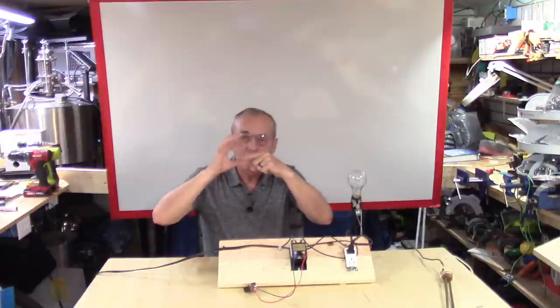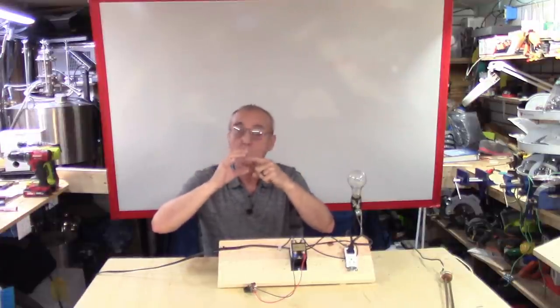This is known as a solid state relay. For lack of better, most of you have seen these before, but a solid state relay replaces the old mechanical relays. And if you're familiar with a relay, it's got two points and it's got a piece of metal filament that goes in between the two points and it makes contact. But that's a physical change that takes place and they tend to wear out and spark and response time. There's a lot of variables that go along with that. But in a solid state relay, that happens electrically. So there's no physical parts that are moving. So it's got an extremely long duty cycle, life cycle. So it will run, it'll probably outlast you.